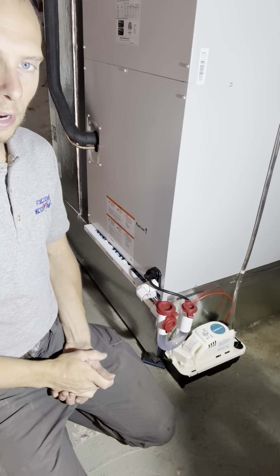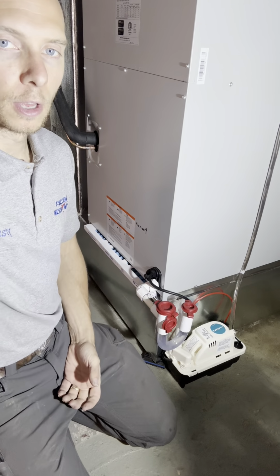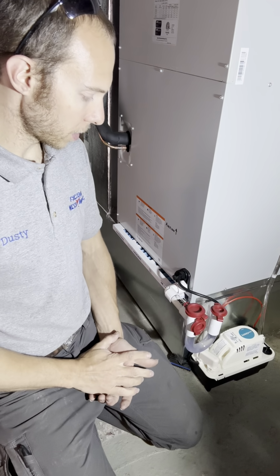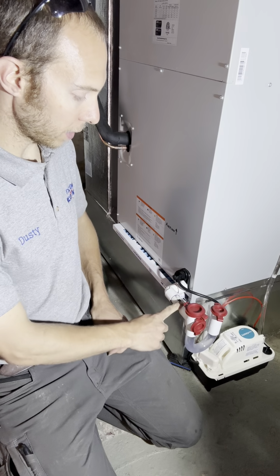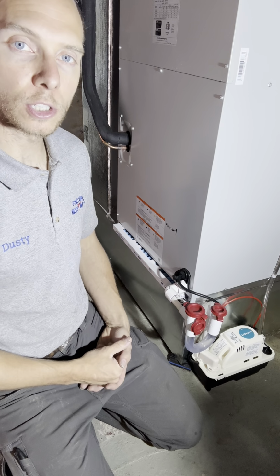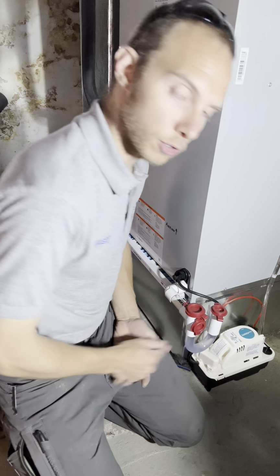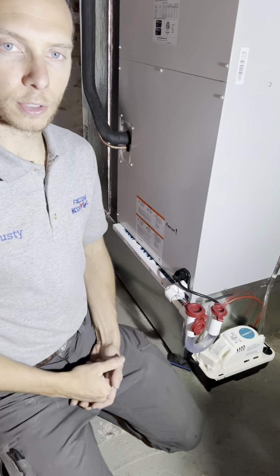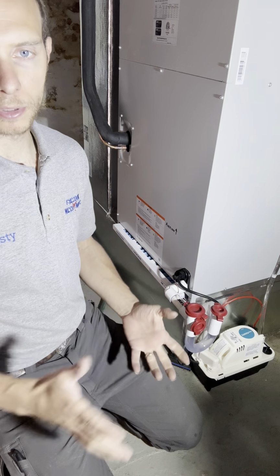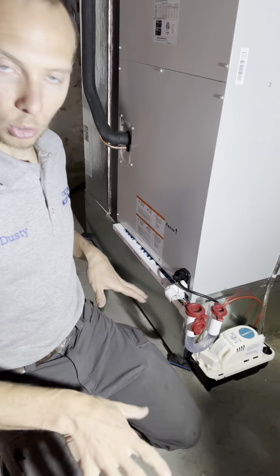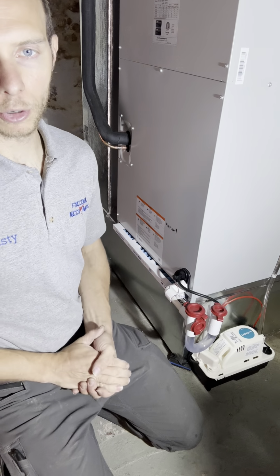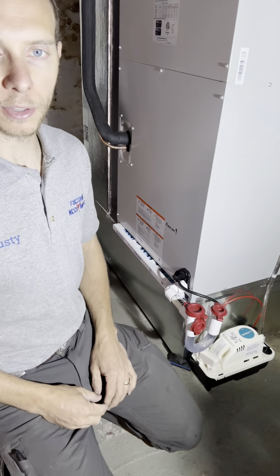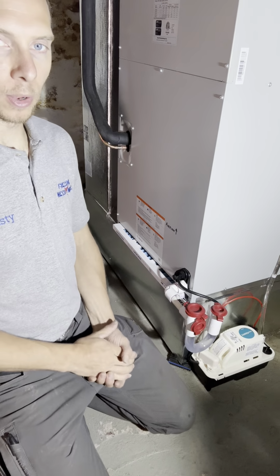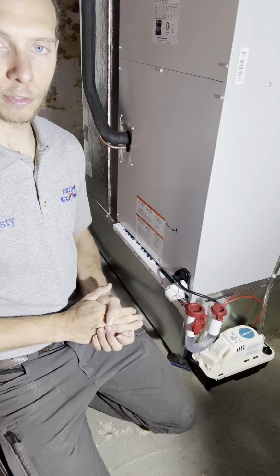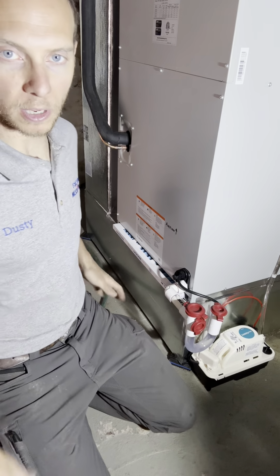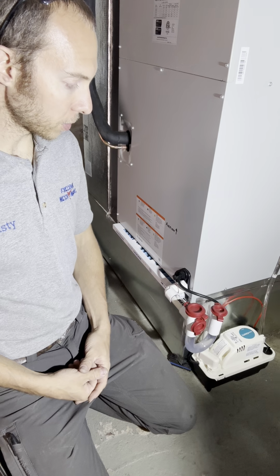So next to the air handler, this particular air handler, there is a condensation system. So out of the coil, we're going to drain the condensation that's collected during the air conditioning cycle, and it's going to run down into a condensation pump. At that point, it's going to pump outside. The reason we would use a pump is if there's not a local drain real close to the unit. You don't want pipes running across your floor, especially rigid PVC or anything like that. So we put a pump on. I don't prefer the pumps, but they are very effective, especially to keep the floor space clean. So very, very nice option there.